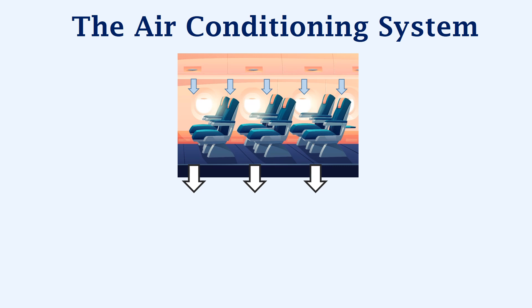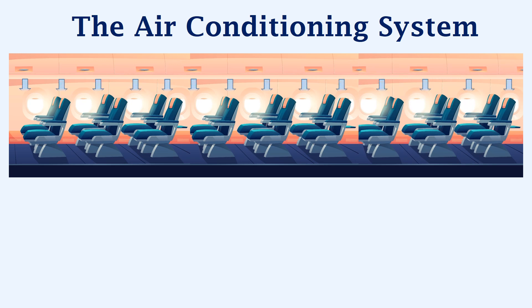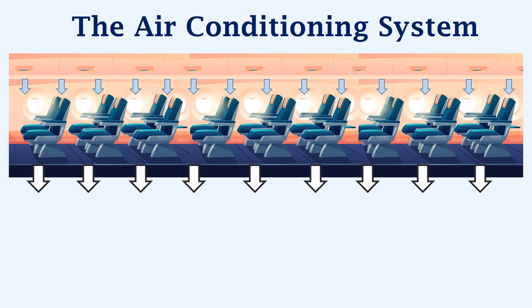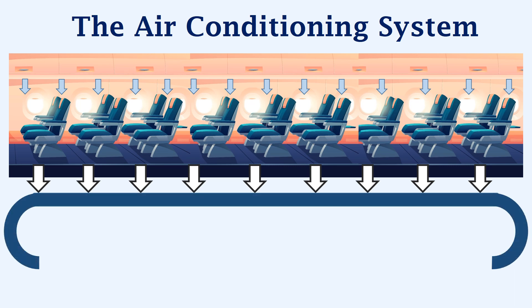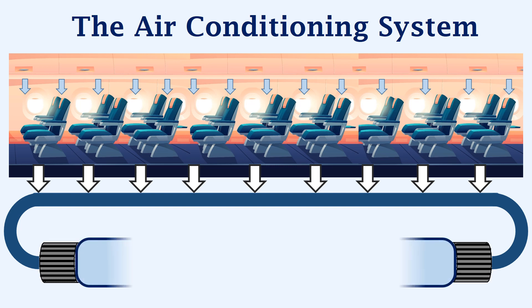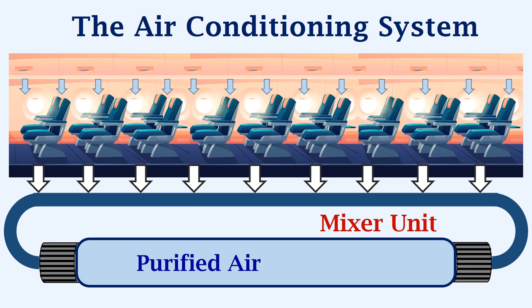This is the impure air, which may contain dust, bacteria, or even viruses. Across the entire cabin section, the air is distributed by vents on the top, and the impure air is sucked out by vents placed at the bottom. The impure air that is collected is sent through specific air ducts for purification. This purification is done by passing the air through the HEPA filter, which is able to remove 99.9% of the impurities. This purified air is sent to the mixer unit, which also receives fresh air from the air conditioning pack. The mixer unit mixes the purified air and the fresh air, which is then sent for distribution in the aircraft.